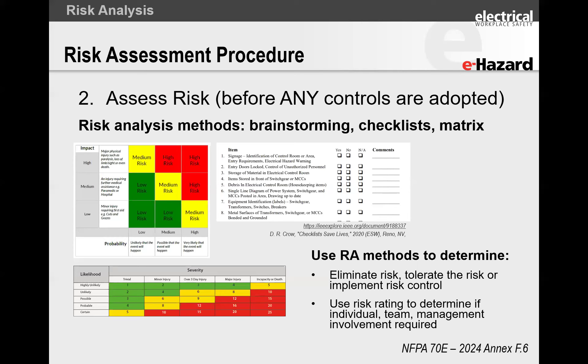Before you get intimidated — your electrician doesn't need a separate assessment for every single task. You can create a two-level system: low risk and high risk; or low risk, medium risk, and high risk. You ask yourself: what makes it medium risk, what makes it high risk? You've got colors — green, orange, red. It's a matrix looking at likelihood versus severity. If I am having an arc flash in my hotel room touching a door handle in winter, the severity is going to be trivial. Although it is almost certain I'll get a static shock, the severity is trivial, which puts it down to a green or yellow.